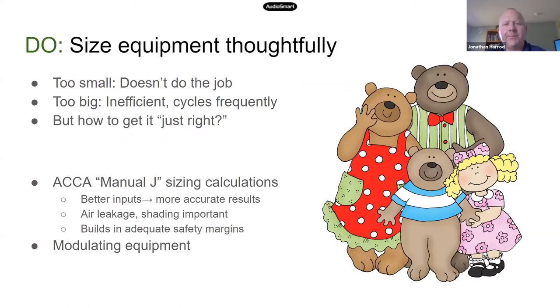So the first big important thing starts back at the design stage, and it's really important to size this equipment correctly. If we put in a system that's too small, and here I'm not talking about physical size, I'm talking about heating and cooling capacity, it won't keep up under extreme weather, and you won't be able to maintain comfort on really hot or really cold days. But bigger isn't always better. If it's too big, you're going to lose efficiency. You're going to end up with a system that cycles on and off frequently. You may end up with temperatures that wander all over the place. So the question is, how do we find just right?